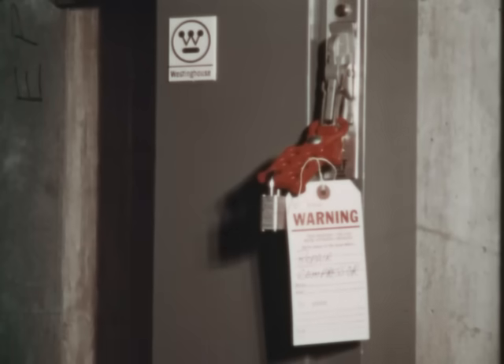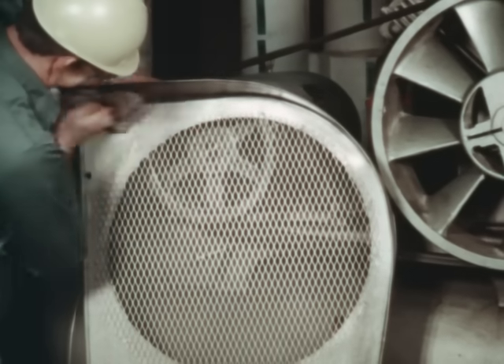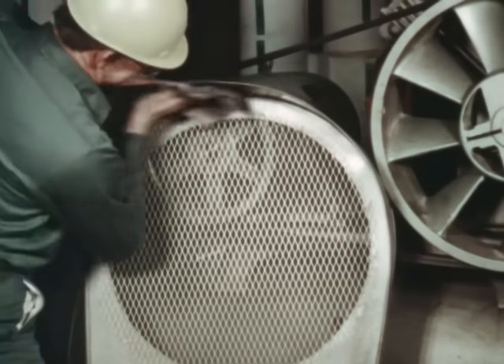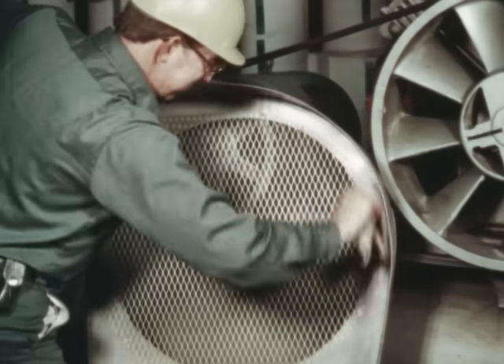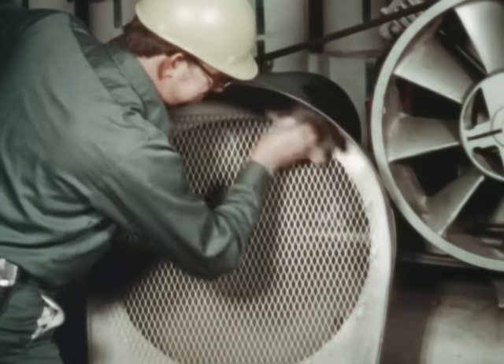Whenever beginning to inspect any type of electrically driven machinery, always lock out and tag the main disconnect of the equipment being worked on. Remove the belt guard and clean it. This will prevent dirt and other foreign material from dropping off the guard and collecting on the belts or in the sheave grooves. The guard also protects the belts from the surrounding outside environment.